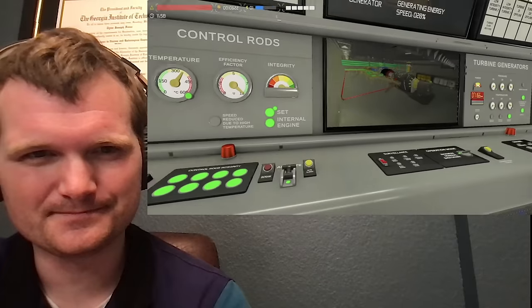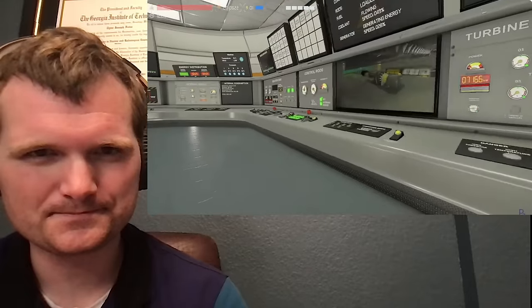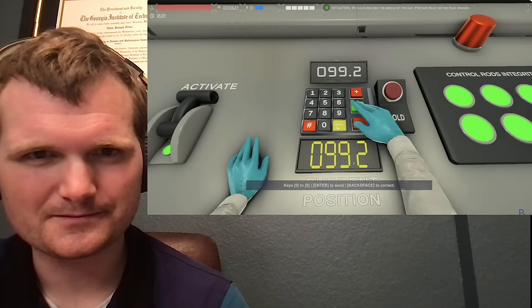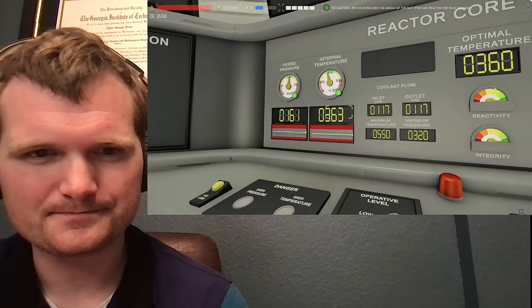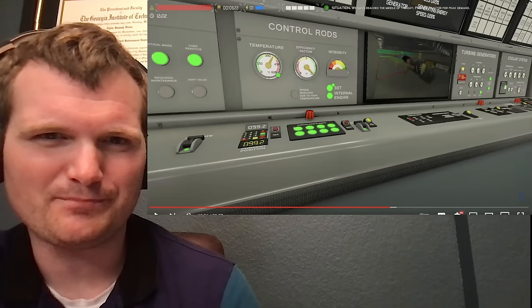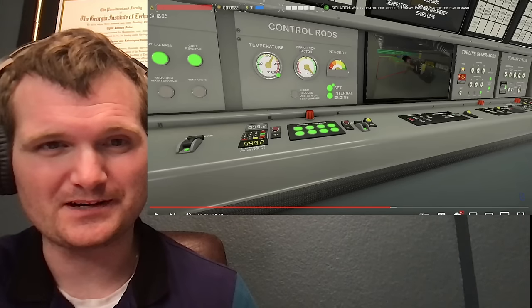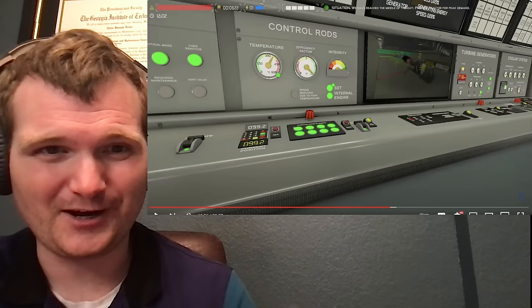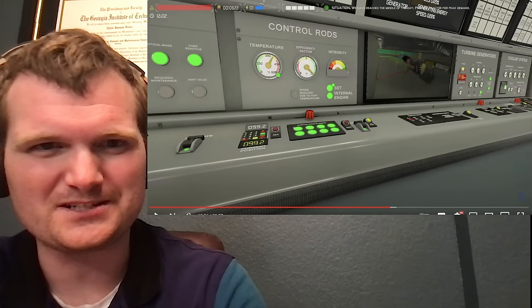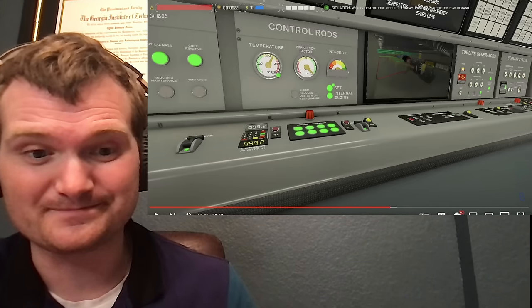So to produce more power, there are a couple of different things we can do. The first is we can increase our coolant speed. If we increase the speed of our coolant, that's basically going to give us the ability to run the reactor a little bit hotter — we're basically just going to pull up the control rods a little bit so we can extract more thermal energy out of it without raising the temperature of the reactor itself. One thing about control rods: this is 99.2 steps — or maybe centimeters or inches — every core design is different. When you come up from an outage, it'll tell you approximately what your full-out position is and where the rods should be as you're raising power. So 99.2 doesn't really mean anything by itself without looking at the nuclear design report.